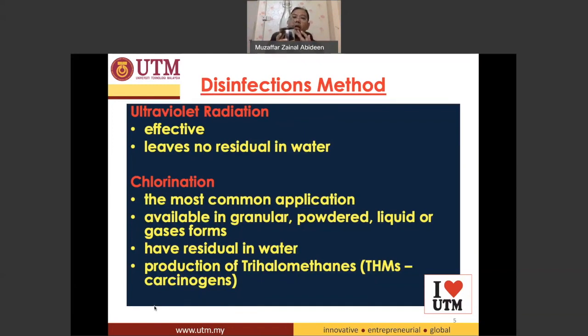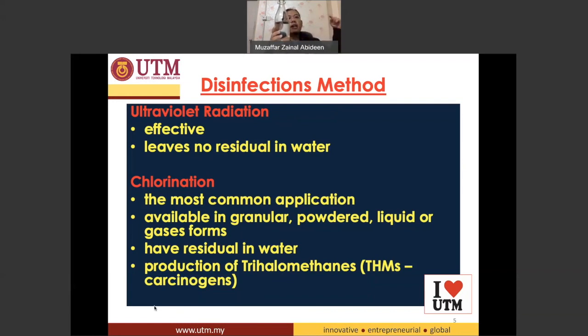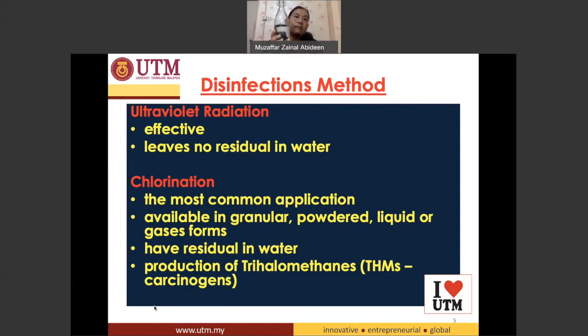However, UV cannot be applied to water that has high turbidity. High turbidity means there is a lot of suspended solid inside the water. When the ultraviolet rays are directed into the water, they will be reflected and deflected by the suspended solids and won't be able to kill the pathogens effectively. Additionally, UV also has no residual effect in the water.